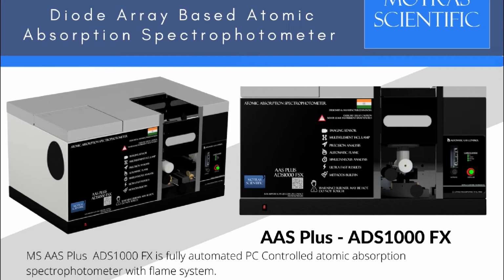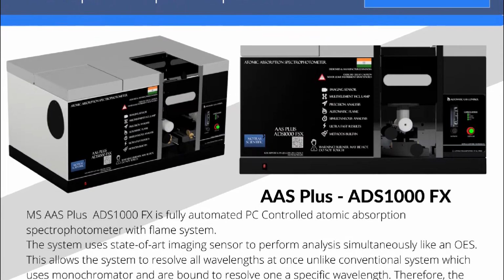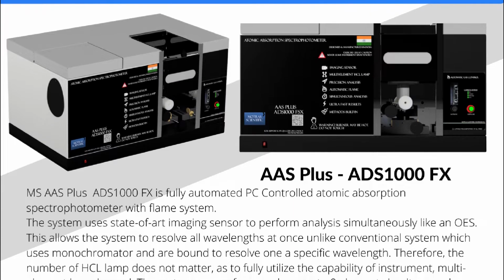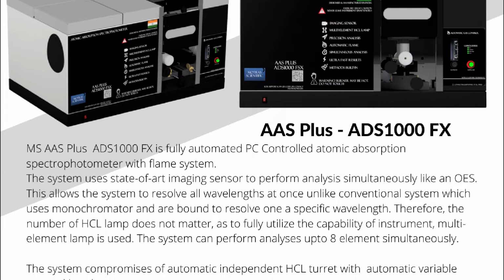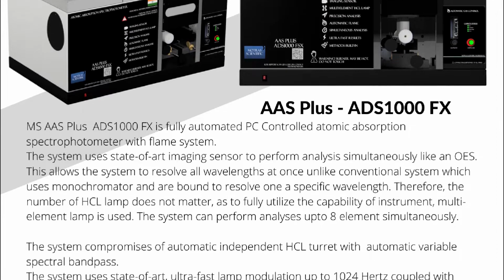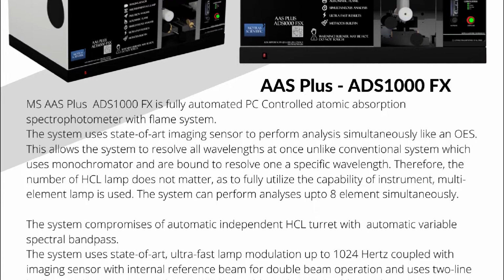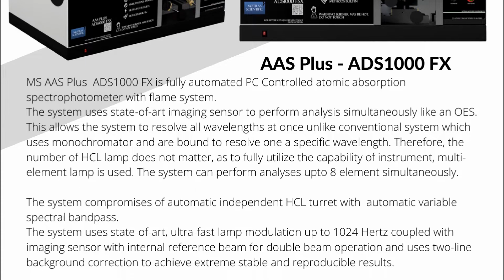Welcome to the demonstration of ADS1000FX Atomic Absorption Spectrophotometer manufactured by Motras Scientific Instruments Private Limited based in Gurgaon, India. The ADS1000FX is a diode array based atomic absorption spectrophotometer which uses a polychromator to resolve and perform analysis for all elements. The system is able to detect and perform on all the wavelengths simultaneously.